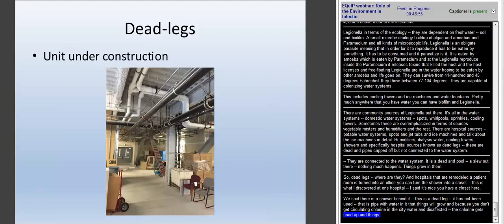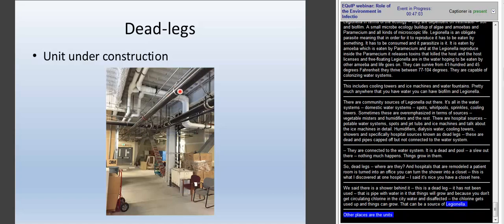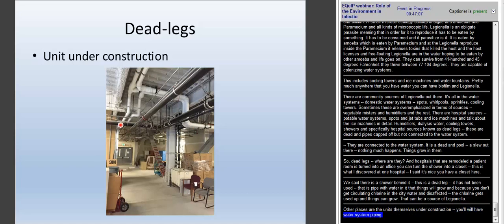Other places are in the units themselves if they're under construction, where you're doing a big tenant improvement, and you'll have water system pipings that run through here, and they're all connected, but they don't get any water service because all the plumbing's been turned off. Well, that is a huge dead leg that'll become an issue once the water gets turned back on.